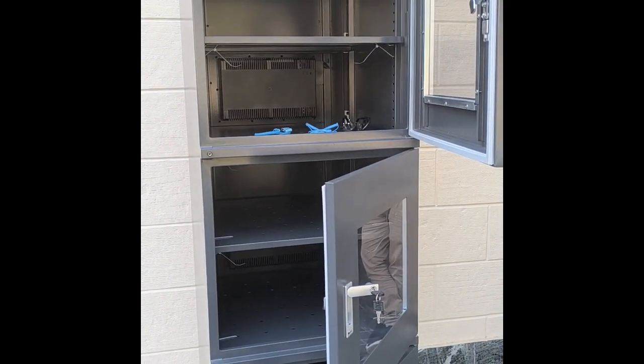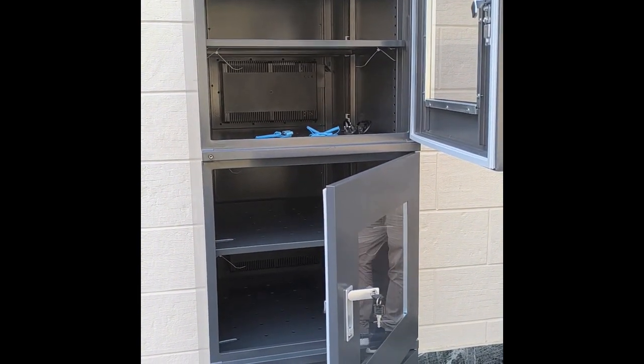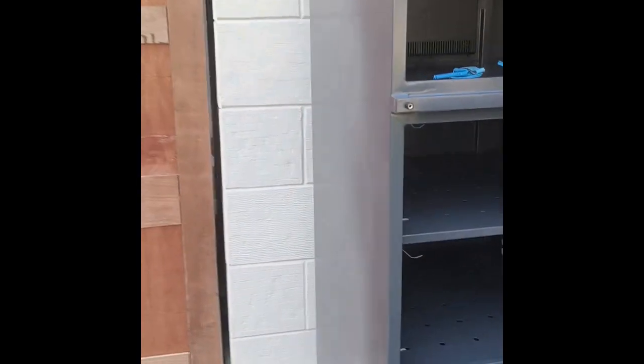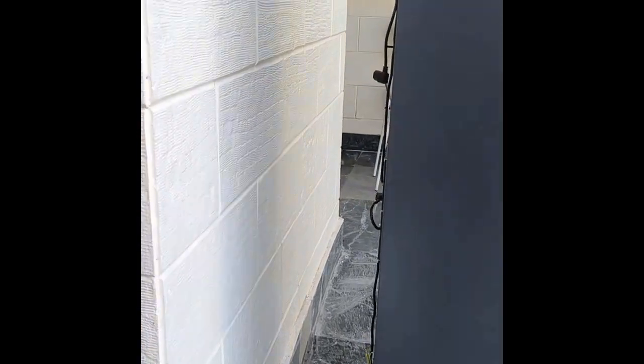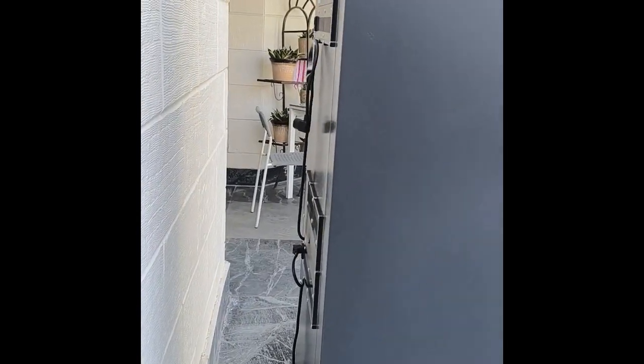One more precaution you need to take: we should maintain a distance of around 30 centimeters from the wall. You can see this dry cabinet is around 1 feet away from the wall. This precaution is taken for smooth air passing and proper functioning of the dry cabinet, as moisture is released from the rear side. So there should be a distance of around 1 feet between the wall and the dry cabinet.